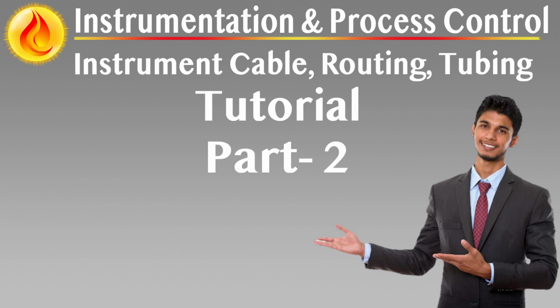Cable pulling and installation methods for integrity assurance. To preserve cable insulation and conductor integrity, cable pulling operations must be conducted in accordance with environmental and mechanical constraints. Pulling at ambient temperatures below 5 degrees Celsius is prohibited due to the risk of insulation cracking.